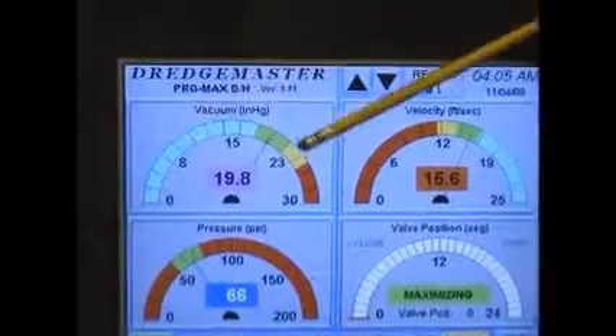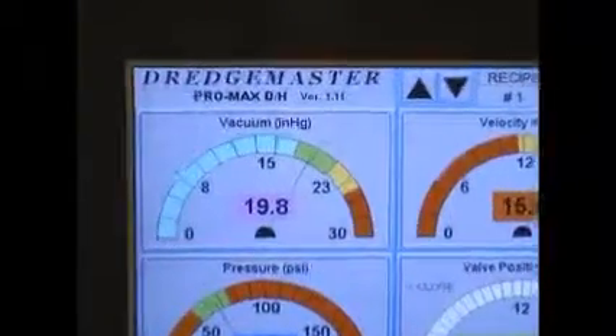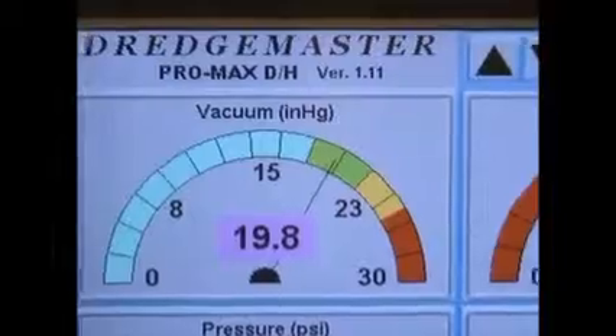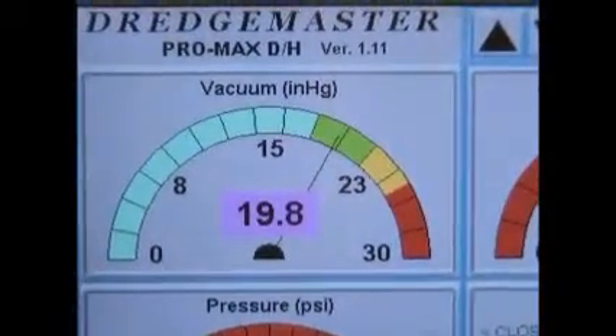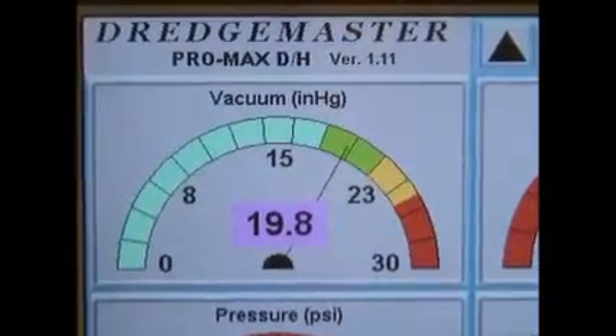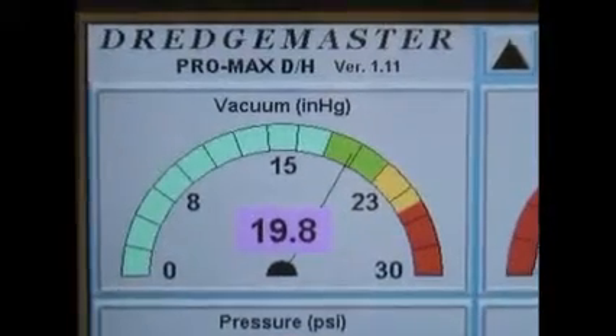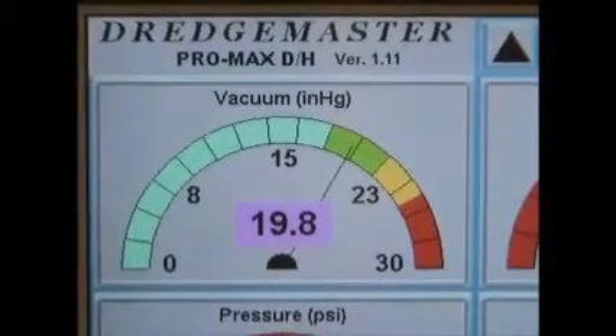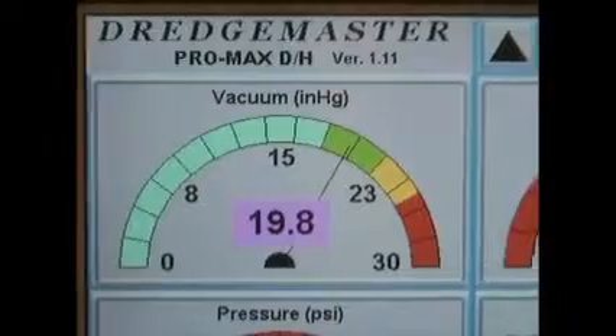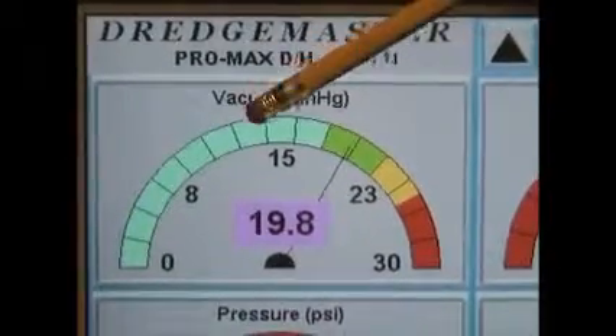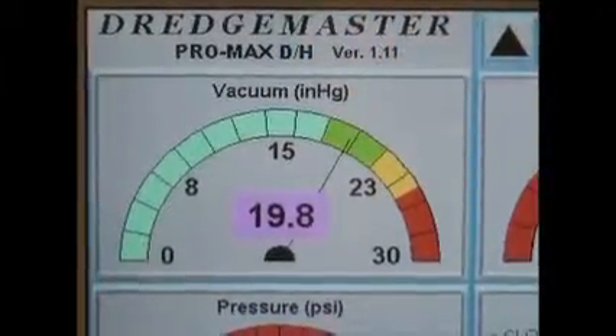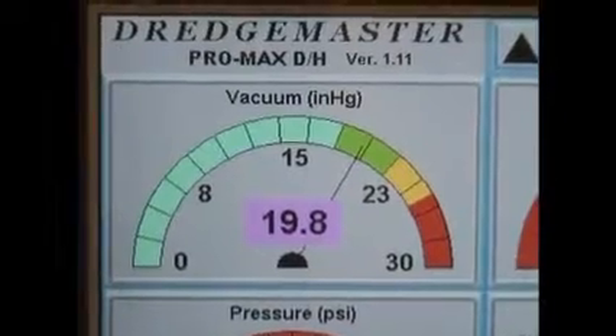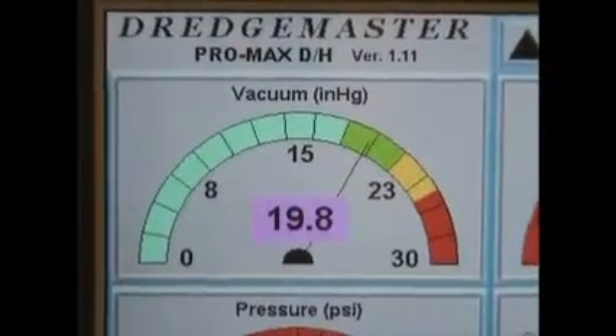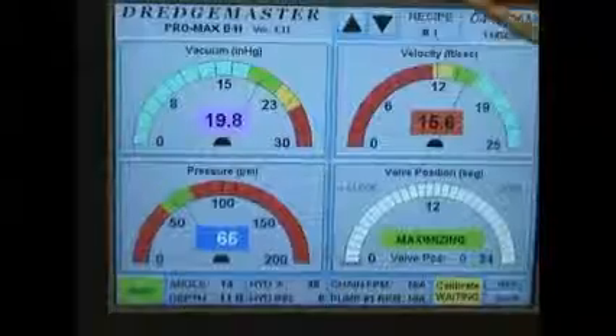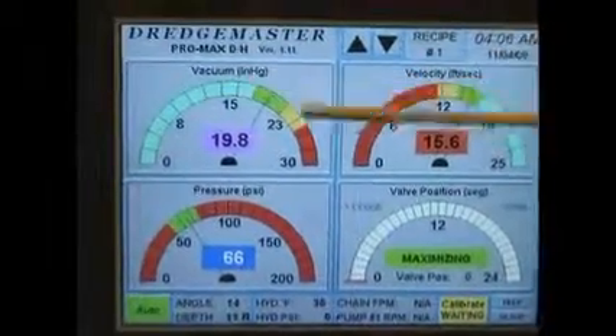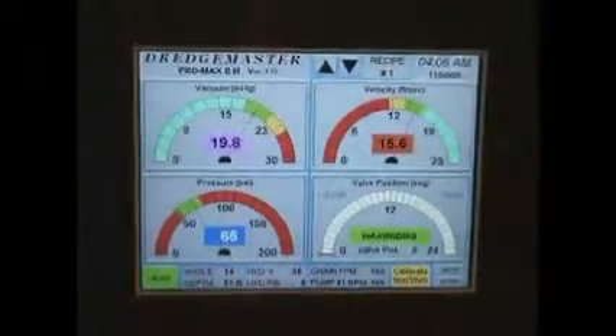Let's look at the color zones on our vacuum gauge. As we all know, different dredges and different deposits require us to have different parameters set at the point where we want the valve to open or where we want the valve to close. All four of these color zones are adjustable, as we'll show you here in just a second. Okay, let's take a look at how we adjust these color zones.